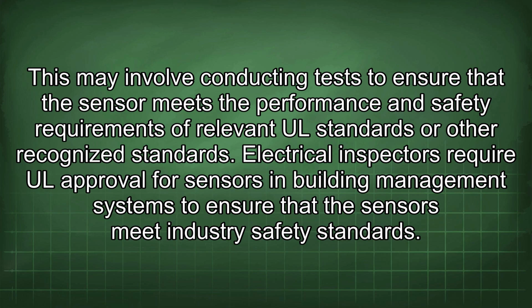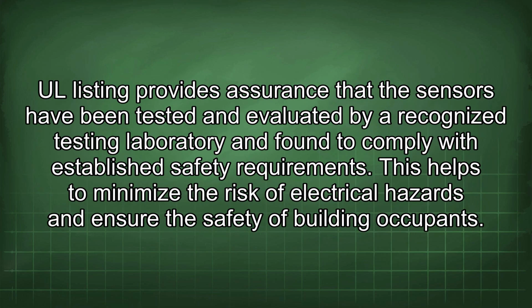Electrical inspectors require UL approval for sensors in building management systems to ensure that the sensors meet industry safety standards. UL listing provides assurance that the sensors have been tested and evaluated by a recognized testing laboratory and found to comply with established safety requirements. This helps to minimize the risk of electrical hazards and ensure the safety of building occupants.